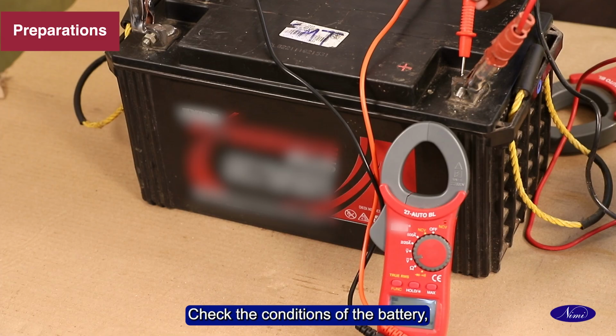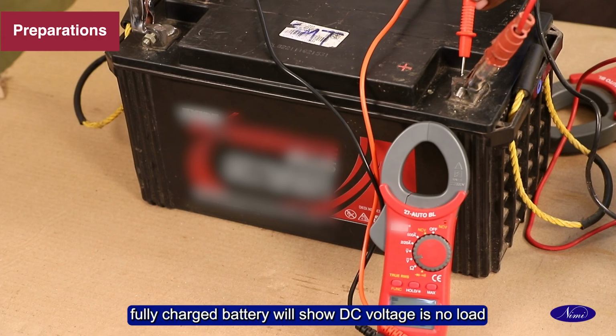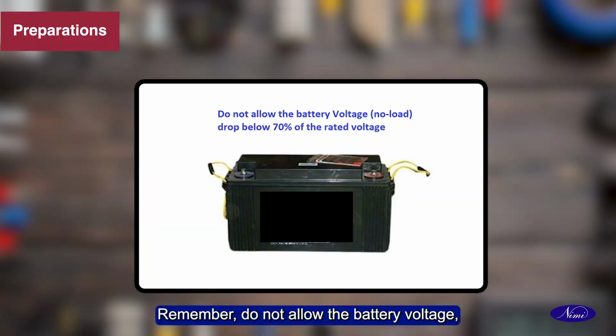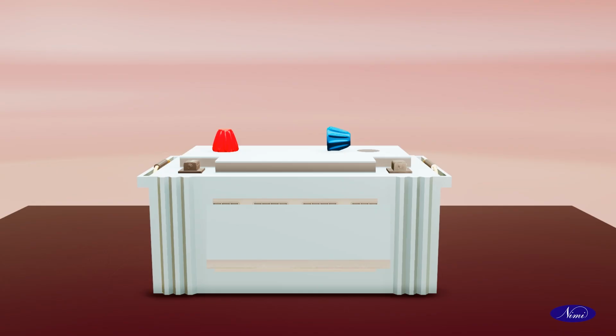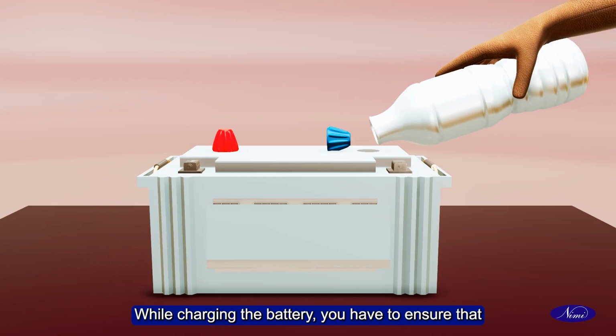Check the conditions of the battery. Fully charged battery will show DC voltage at no load about 20% more than the rated voltage. Remember, do not allow the battery voltage at no load to drop below 70% of the rated voltage. If it is so, then reviving the battery is difficult. While charging the battery, you have to ensure that it is topped up with distilled water and caps are removed for easy gaseous out of the cells.